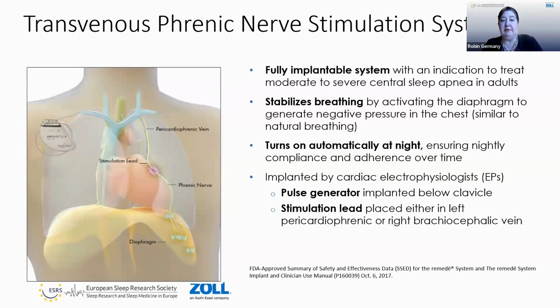It's a fully implantable system. It's implanted typically by a cardiologist in the same place that they put in pacemakers and defibrillators under conscious sedation. The device itself has one stimulation lead that's either placed in the pericardiophrenic vein, which runs right next to the phrenic nerve on the left side. It's in the same bundle, or in the right brachiocephalic vein. I don't know if you can see my cursor, but right up here. So next to one of the phrenic nerves. And on the highest level, it's designed to stimulate one of the phrenic nerves to move the diaphragm. And the concept is that it's going to stabilize breathing. And we'll look at that just a little bit further. So it's a different concept. Think of negative pressure system versus positive pressure system.